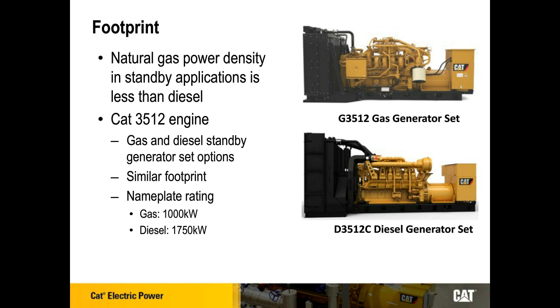Here's a good example: both pictures show 3512 Caterpillar generator sets, meaning 12 cylinder engines. One's a gas engine on top, the diesel's on the bottom. Both are similar size engines, but the gas generator gets about 1,000 kW out of it, while the same footprint diesel gets about 1,750 kW. So we can get more power out of the same size footprint on the diesel side. If space is a consideration and you have a tight footprint to fit a product into, diesel makes a better option for those applications.